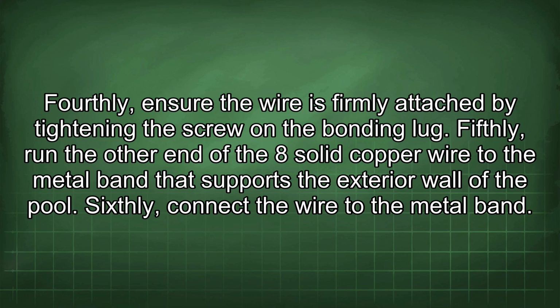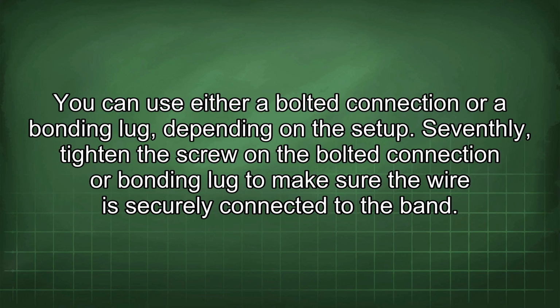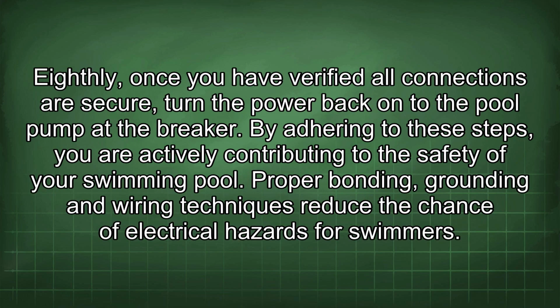Fifthly, run the other end of the 8-solid copper wire to the metal band that supports the exterior wall of the pool. Sixthly, connect the wire to the metal band. You can use either a bolted connection or a bonding lug, depending on the setup. Seventhly, tighten the screw on the bolted connection or bonding lug to make sure the wire is securely connected to the band. Eighthly, once you have verified all connections are secure, turn the power back on to the pool pump at the breaker. By adhering to these steps, you are actively contributing to the safety of your swimming pool. Proper bonding, grounding, and wiring techniques reduce the chance of electrical hazards for swimmers.